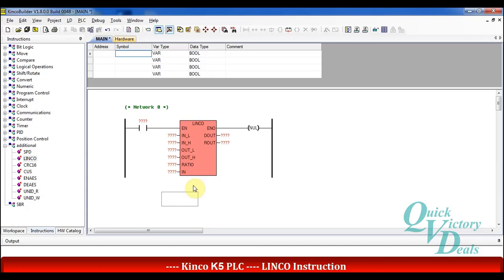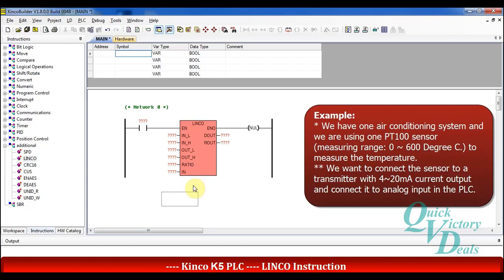We will continue with one example. In one air conditioning system we are using one PT100 sensor with a range of 0 up to 600 to measure the temperature. This sensor is connected to a transmitter with a current output. The final 4 up to 20 mA current will connect to the analog input of the PLC.